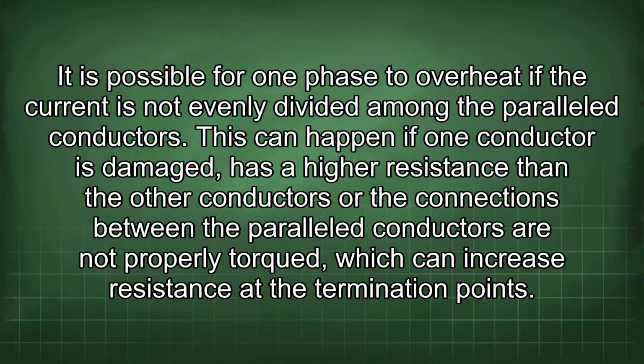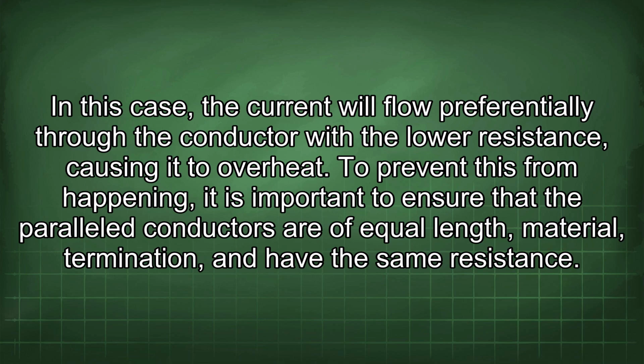It is possible for one phase to overheat if the current is not evenly divided among the paralleled conductors. This can happen if one conductor is damaged, has a higher resistance than the other conductors, or the connections between the paralleled conductors are not properly torqued, which can increase resistance at the termination points. In this case, the current will flow preferentially through the conductor with the lowest resistance, causing it to overheat.